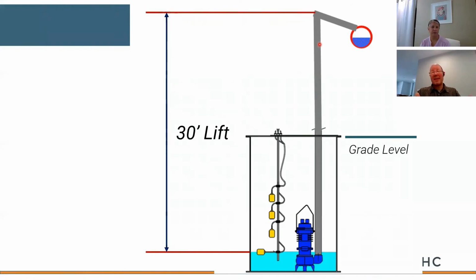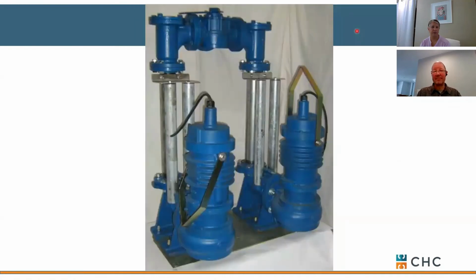So if your head calc is accurate, then we can select this motor horsepower just based on that 30 foot of rise. We'll never see 25 or 29 because we won't be moving water out of our basin at that point. Kind of self-balances the pump if you think about it. Okay, but all that depends on your safety factor and other conditions in the field. But it's just one mindset when you're selecting sump and sewage. Okay, I'll get off of that horse.